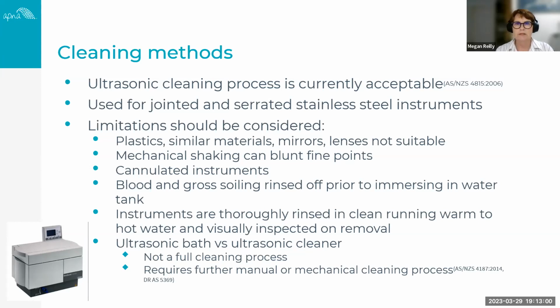So when we consider using ultrasonics, we have to also be aware of the limitations, and there are quite a lot of limitations associated with ultrasonic cleaning. Now, we know that this process actually subjects your instruments to high frequency, high energy sound waves, and that causes the soil to be dislodged or sufficiently loosened so that when you undergo that thorough rinsing process, it enables the removal of the soiling. So we can see that there are lots of things that we can't put into an ultrasonic cleaner. Because of the mechanical shaking that occurs, it does tend to blunt fine points. You can't put cannulated instruments into what I refer to as an ultrasonic bath, unless it is an ultrasonic washer that is specifically designed with connections that can be added to your cannulated instruments.